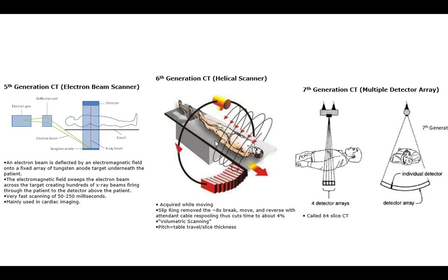You'll get a couple, right? So you would imagine the geometry is pretty similar between these tiny areas. So, if you're catching part of a rib, you'll catch part of the rib in the next one. So it will actually be able to use that inter-sampling between there to smooth it out. You actually get a better quality 3D image by doing a helical scan than you do by a point and sample, because you avoid that horrible inter-sample problem, and you're able to spread them off each other.